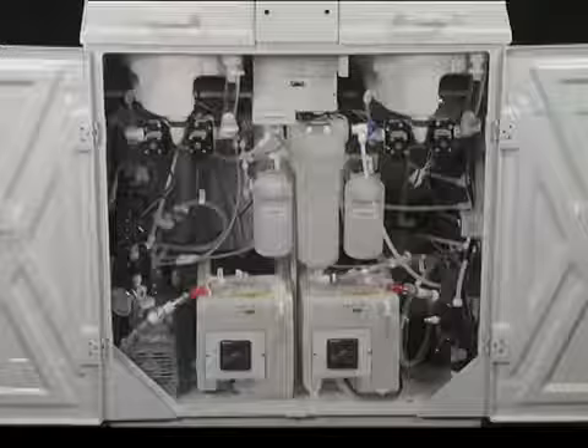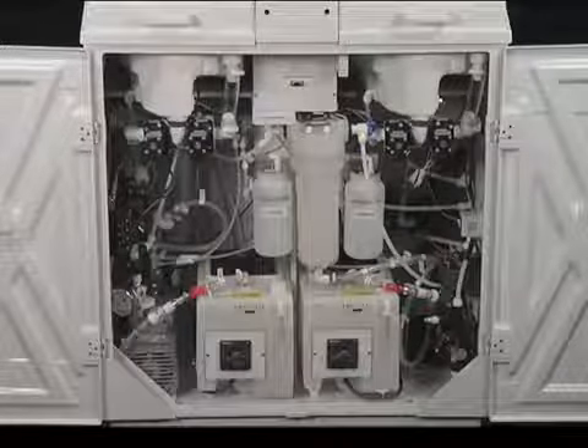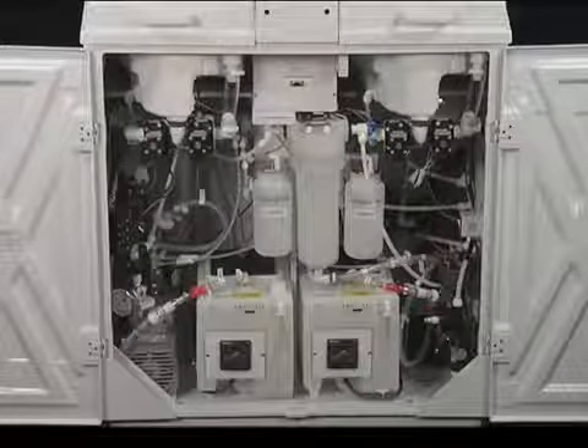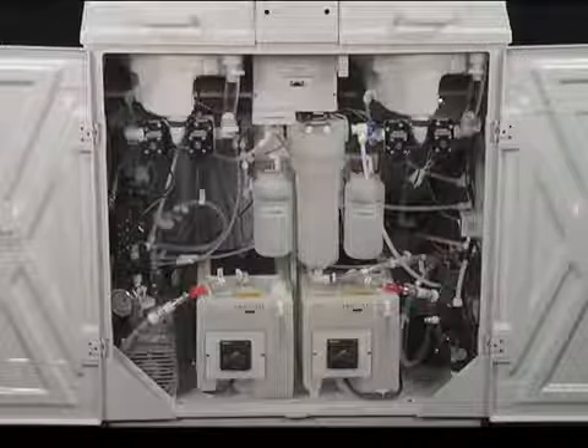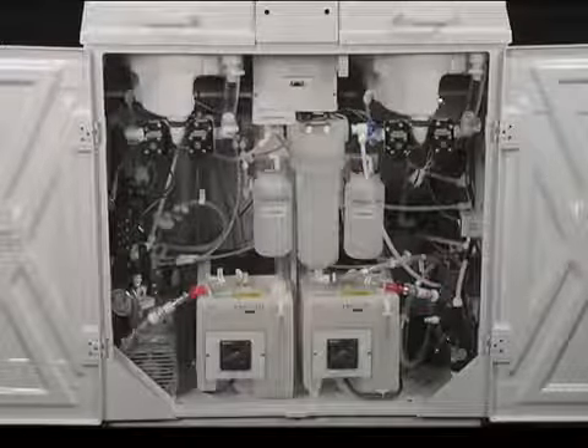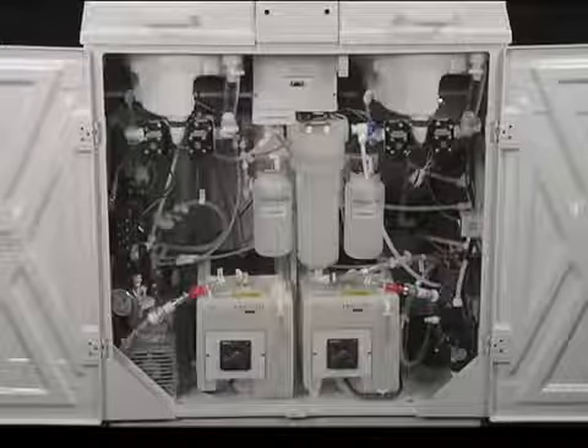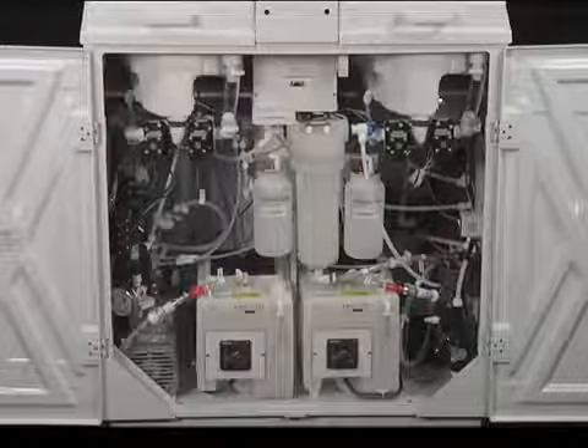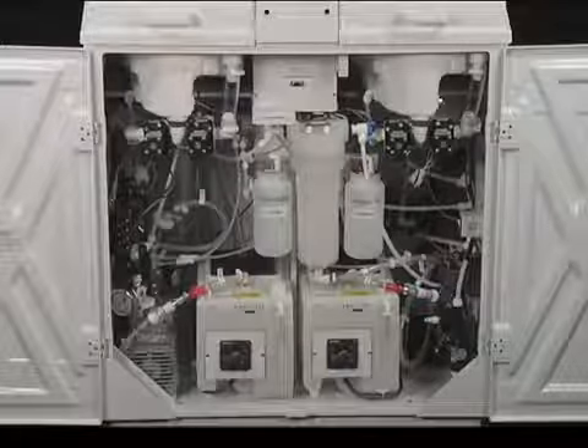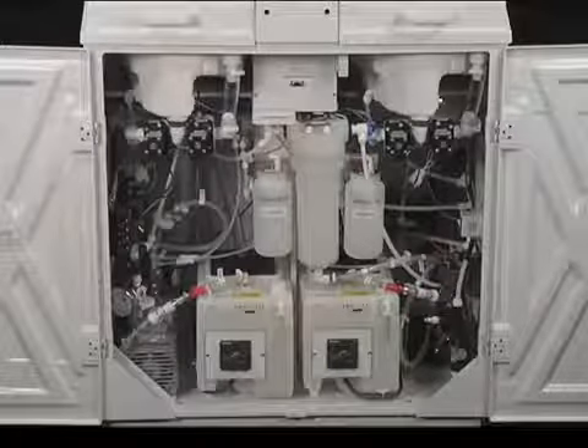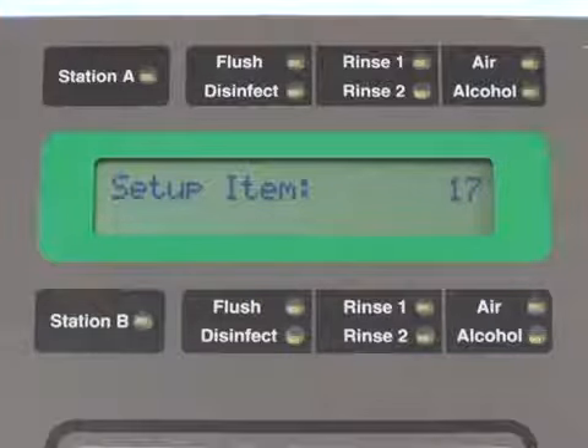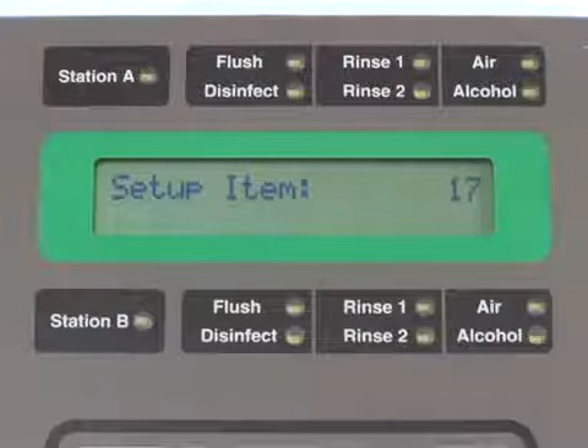Waterline treatment includes sanitization of the filter and lines for approximately 1 hour or for the time programmed for the chemical used for sanitization. The sanitization time is factory set. If you choose to sanitize the water lines for a different contact time, contact technical support or a clinical specialist to make the adjustment. The time remaining can be periodically checked with Setup 17.